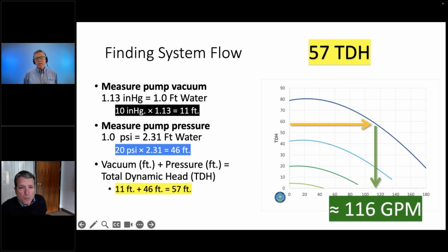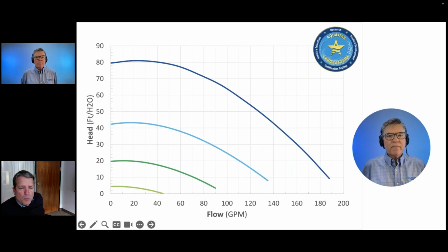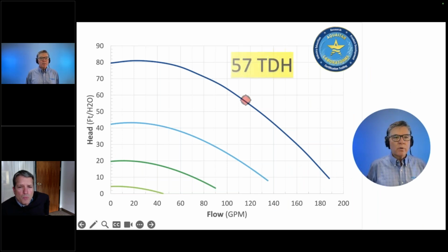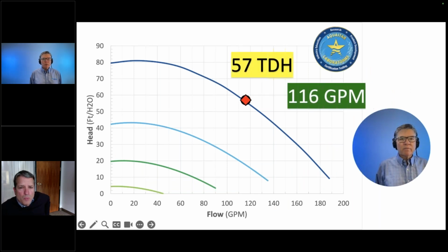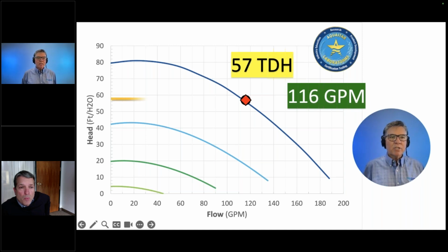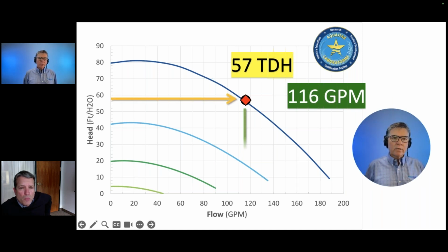This is extremely accurate and accepted by health departments to validate public pools when they don't trust flow meters or just want to validate what the pump is actually doing. So this is a very accurate way of finding out what your pool is doing, and once you know this number, we can do a lot of things with it. This is a pump curve, and we look up that 57 TDH on the left, and then we go down and find out that it's 116. So that's how this tool is used.